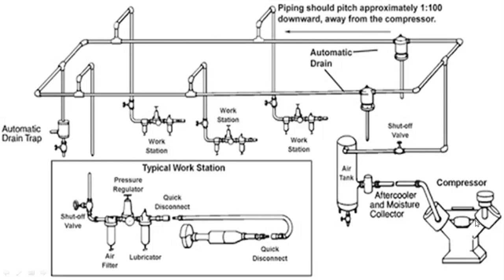In the entire process plant, we have pipelines running all around with different workstations connected through the ring main system. In this typical layout, we have a two-stage compressor, an aftercooler going to an air reservoir tank, shutoff valves at different stages, connection to the ring main, and automatic drain pipes to remove moisture from the air. From this workstation, you can use it for different kinds of pneumatic tools, instrument systems, control actuators — all tapping air from the ring main spread throughout the length and breadth of any process plant.